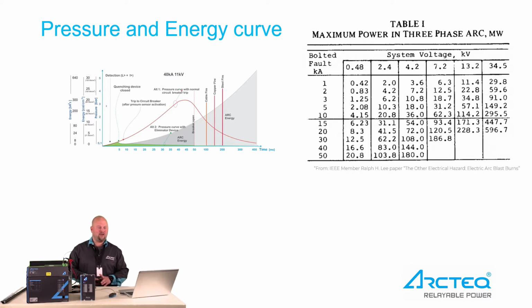In the early 1980s, Ralph Lee wrote a paper, The Other Electrical Hazards: Electric Arc Blast Burns. In that paper there was also this maximum power in a three-phase arc, in megawatts, as an example, to imagine how much arc fault energy there can be. If the fault current is at some level, let's say 50 kiloamps, and depending on the voltage level, for example here 480 volts, the amount of energy is already 20 megawatts, which is a lot.